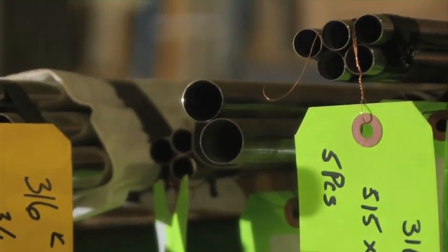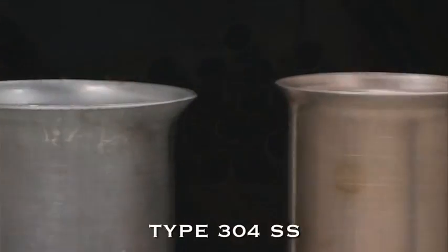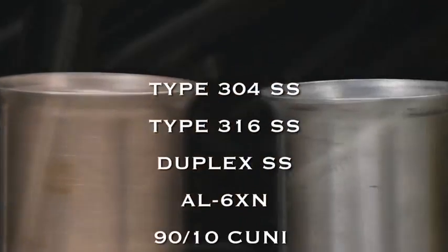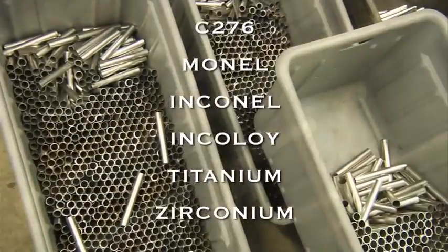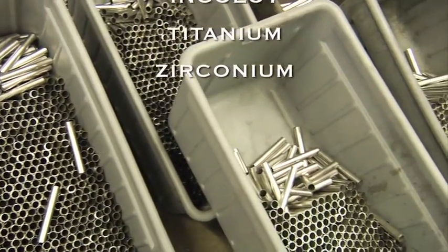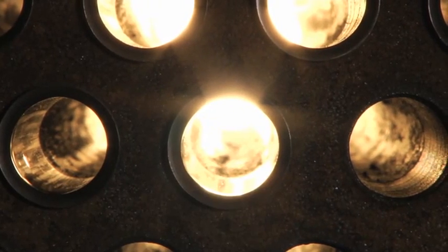Material selection is critical and CTI is able to provide sleeves in many different alloys. The choice is typically a superior but compatible alloy to that of the original tubes. This will increase the erosion corrosion resistance, yet maintain galvanic compatibility.